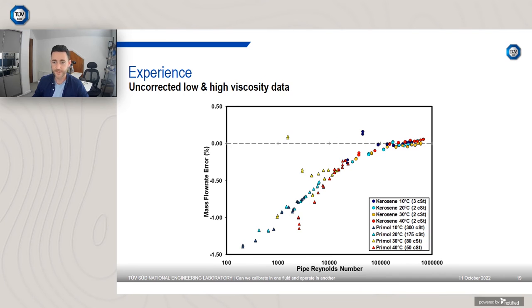just by chance. If we plot it against pipe Reynolds number, so we calculate the Reynolds number, which is obviously the ratio of your inertial and viscous forces. I'm not going to go into the equation for that, but hopefully most people are aware of Reynolds number. If you plot it with respect to Reynolds number for the geometry of the pipe, rather than the Coriolis tubes, so this is the pipe Reynolds number, as said here on the x-axis. You can see there's a clear trend with respect to Reynolds number. So this is the same data, the kerosene and Primol data from the last two slides. You can see there's quite a clear trend with respect to Reynolds number.